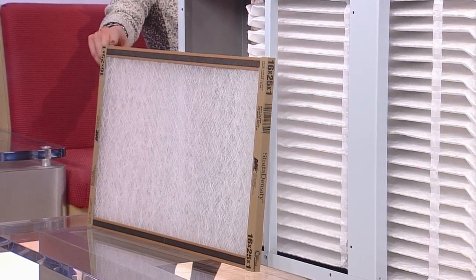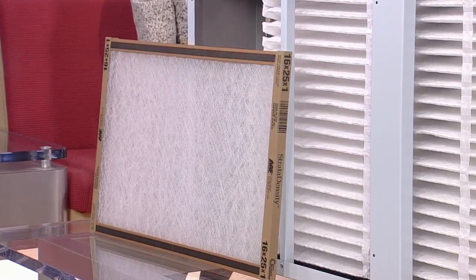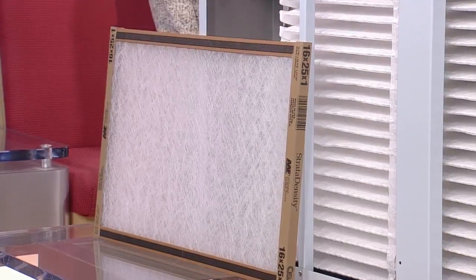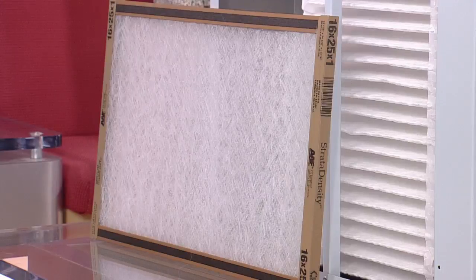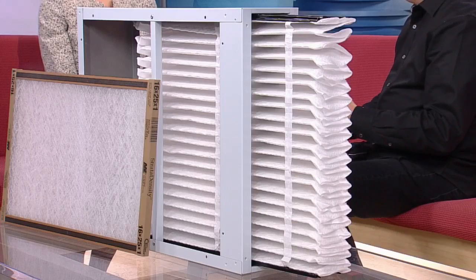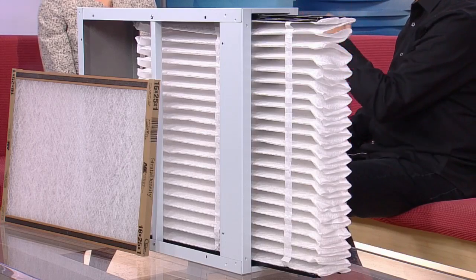This first one is not the best one, it's a 1-inch filter, and it's only about 10% efficient. So most of the dirt and dust circulating through your house, through the furnace, is going right through that filter. This one here is a 4-inch pleated media filter, 80 to 90% efficient at taking out the dirt, dust, pollen, and spores going through the airstream. It's massive, nothing is going to get through there. It's a pleated filter, so it's got a lot of surface area to catch a lot of those particles.